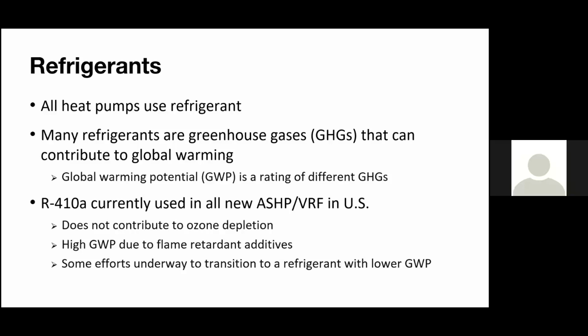Then the chlorine starts to attack the ozone. So we had issues with refrigerants hurting our ozone layer. The Montreal Protocol came along, and we essentially phased out all CFCs and HCFCs. So all refrigerants with chlorine are all gone, including R22, which you might be familiar with. That is an HCFC. So as of January 1st, 2020, you can't even buy any R22 unless it's recycled.